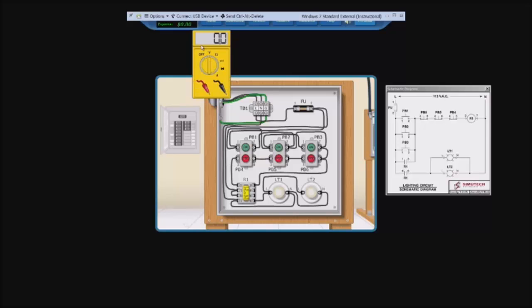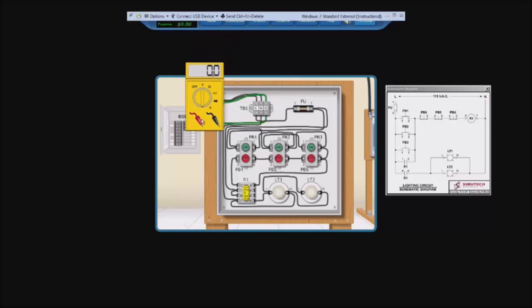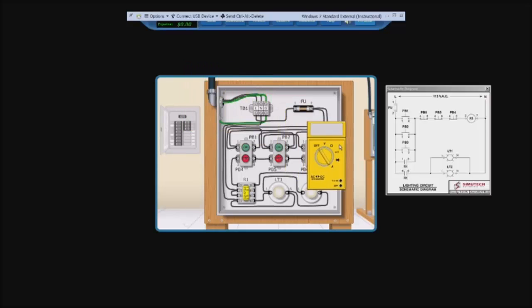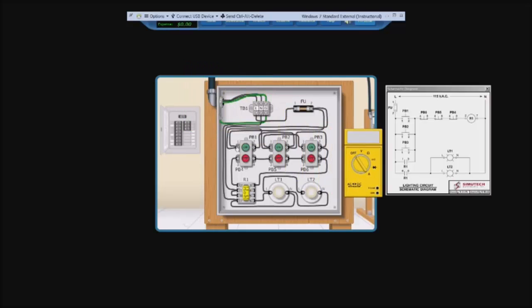So we will go to voltage first, put our black lead on ground and our red lead on fuse one. We have power to the beginning of the fuse. Do we have power on the other side of it? No, which is not a good thing because that means that our fuse is likely blown.